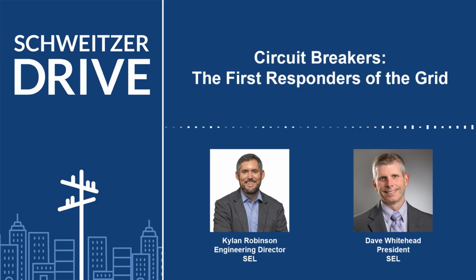I bet you want to talk about our traveling wave technology, and it can detect a fault in, say, a millisecond or two. And then we've got to wait, probably for a good circuit breaker, there's like a 2-cycle, right? So that's 32 milliseconds. So we do it in 1 millisecond, then we wait around for 32 more milliseconds to clear a fault. Do you see, if we're looking forward, new technologies where the circuit breaker can match the speed of the relay now?